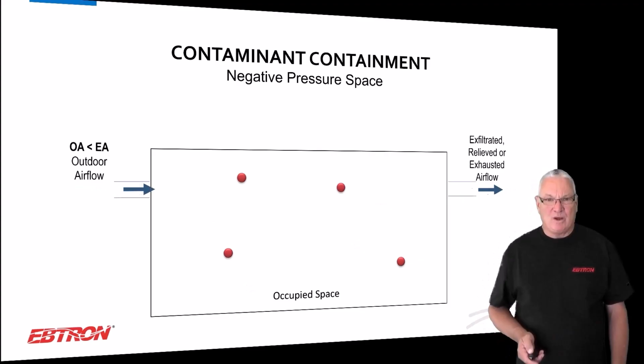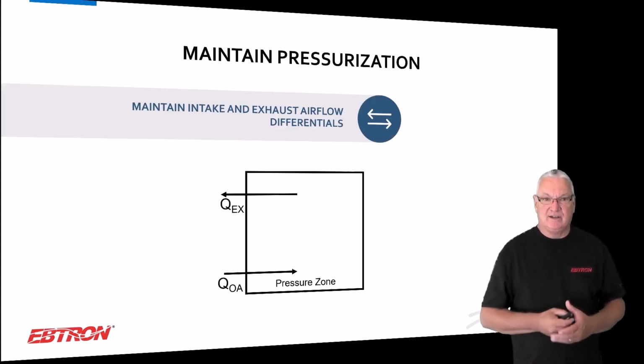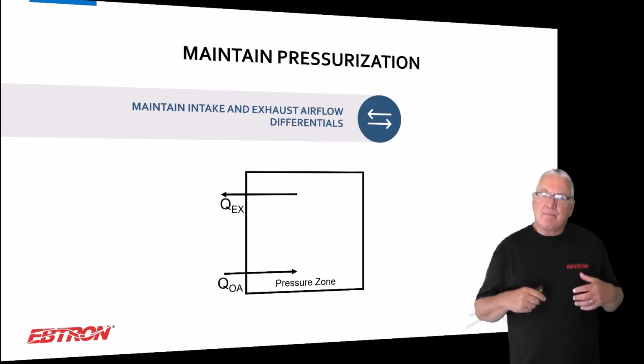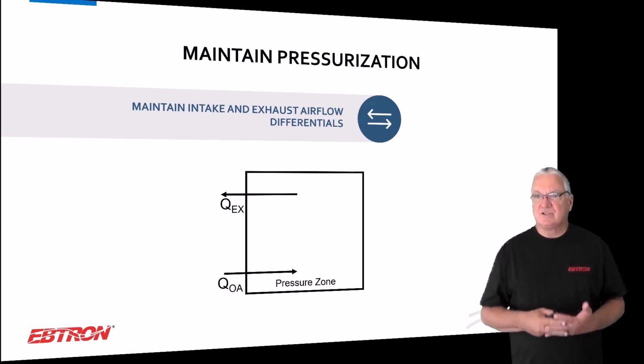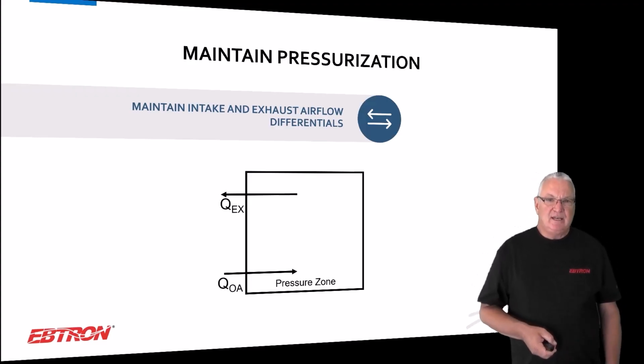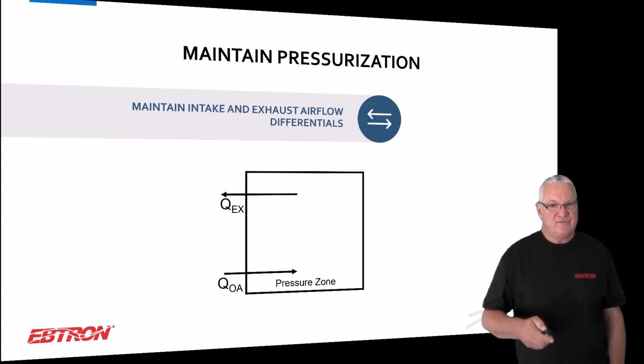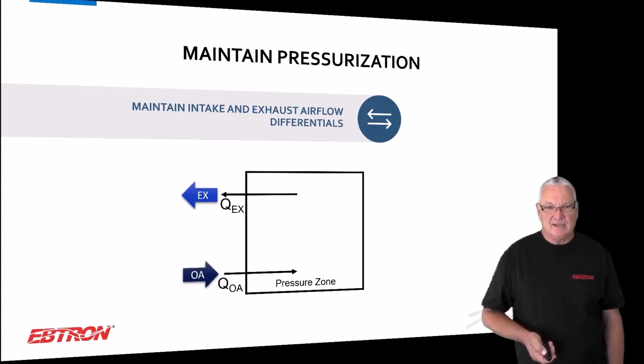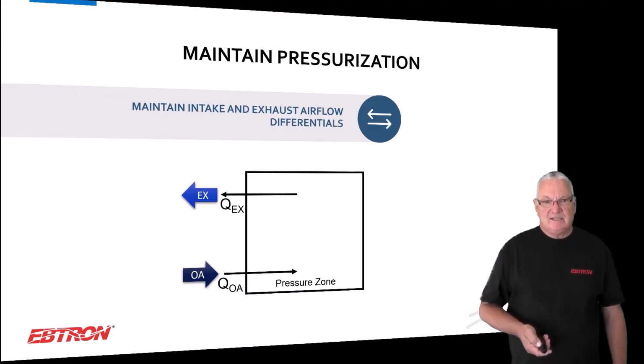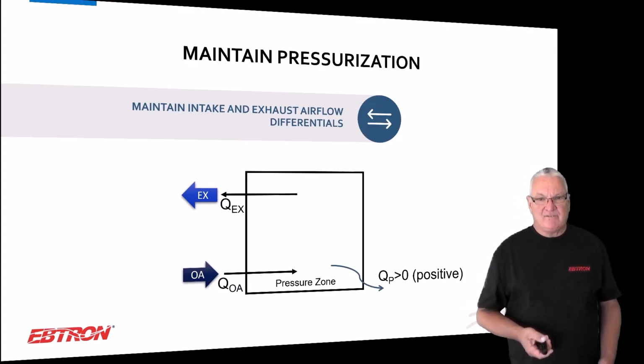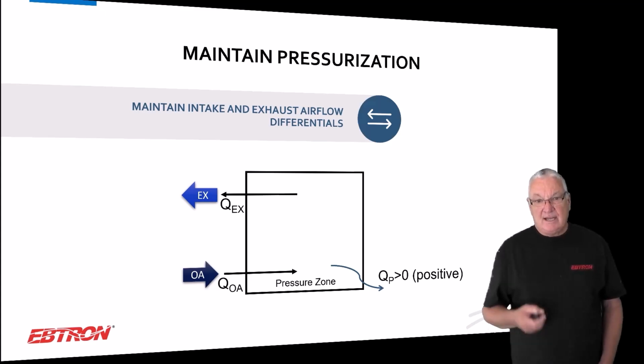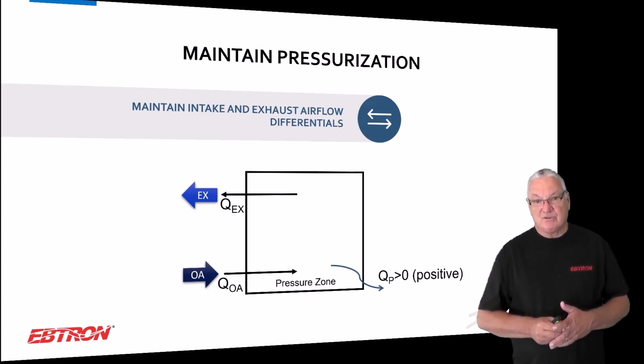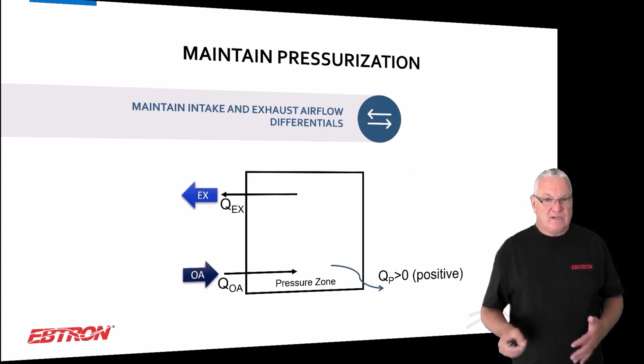Okay, so what are we really doing? What are we doing to do that? Even though we talk about pressure, we've called it pressurization for so long, that's just what we call it. But it's really not so much pressure as flow, okay? So if we have a pressure zone and we have outside air coming in and exhaust air going out, maybe we do or don't have powered exhaust out or relief. But the bottom line is, if I have more mechanical ins than outs, then I've created a positive pressurization flow. And that positive pressurization flow would result in a measurable pressure drop at points in the space, but it's really the pressurization flow that we want to control.